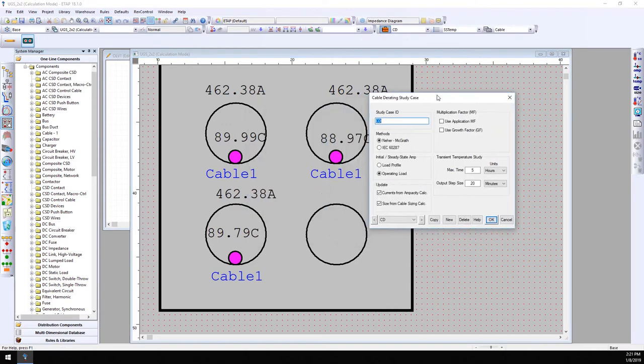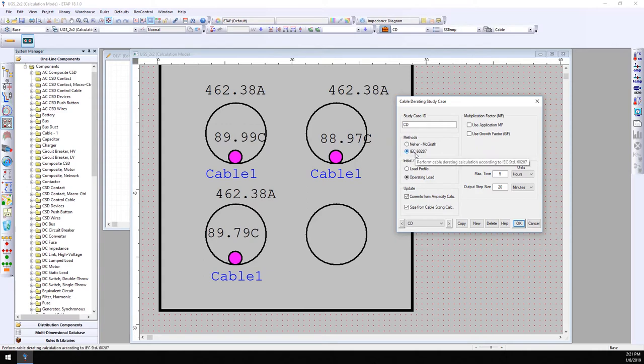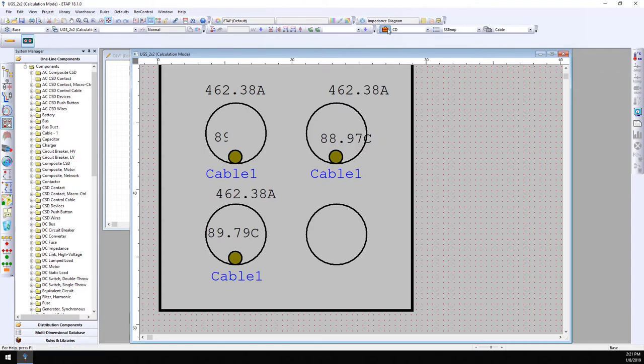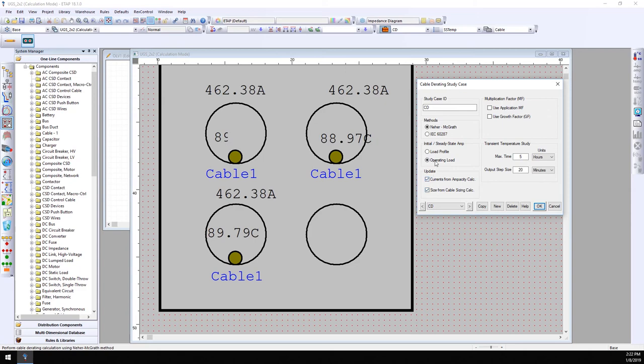Looking at the study case, there are two methods available: the Neher-McGrath method and, for 50 Hz IEC projects, the IEC 60287 method. When selecting IEC 60287, only the steady-state temperature option is displayed, as the other optimized options like Uniform Ampacity are not part of that standard and are automatically disabled. For access to the optimized calculations, use the Neher-McGrath method.